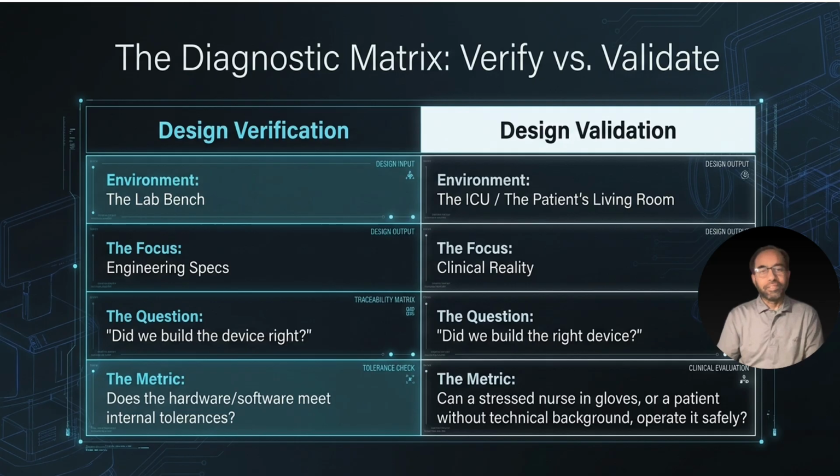So how do you fix this problem? Bring clinicians, patients, and human factors experts into the loop early. Run simulated use tests with rough prototypes long before you freeze your design. Research how other similar devices have failed before, then apply risk mitigation proactively.